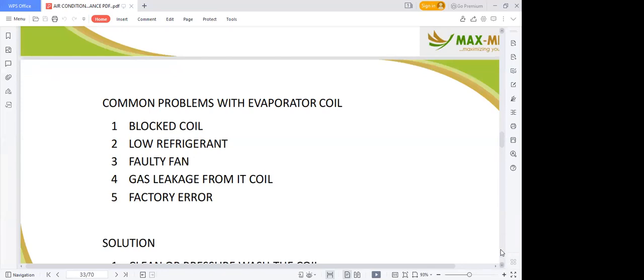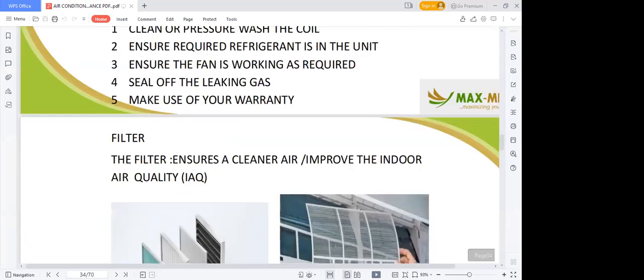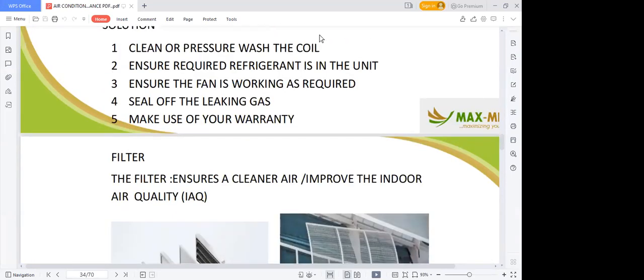So what are the solutions? These are the solutions. Clean or pressure wash the coil. Once you notice that the equipment is not being washed, your technician needs to pump down, uninstall the indoor unit, take it out to pressure wash it, dry it and bring it back. Then open up your nozzle beside it, then you pump back, then switch on. Ensure required refrigerant is within the unit. Ensure the fan is working as required. The fan must work well. It must not wobble while working. It must work without producing noise. Then that is fine. Seal off the leaking gas. Then make use of your warranty if there are factory errors.